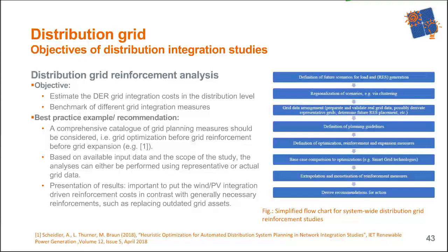As a best practice, our recommendation is that you need a very comprehensive catalog of grid planning measures. You should consider grid optimization before grid reinforcement and before grid expansion, so you have a lot of options: parallel lines, additional transformer stations, additional voltage regulators, volt-var control, and so on. There's also an approach showing that automation in distribution grid studies is getting more and more important, because we're getting more and more options.